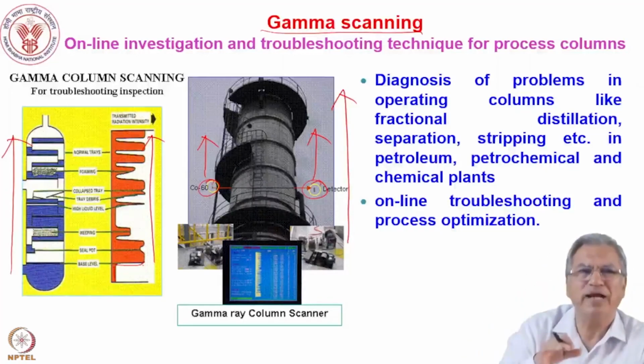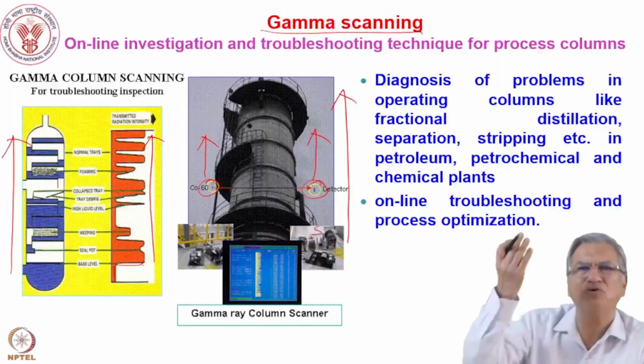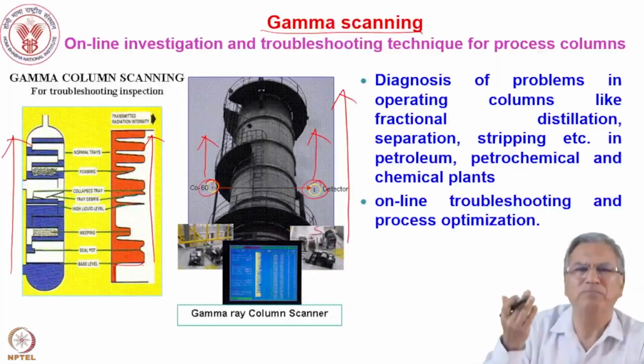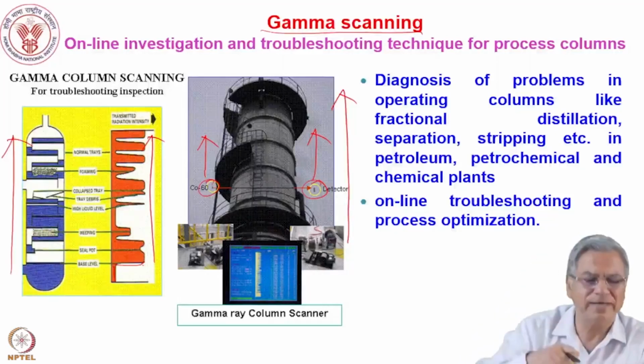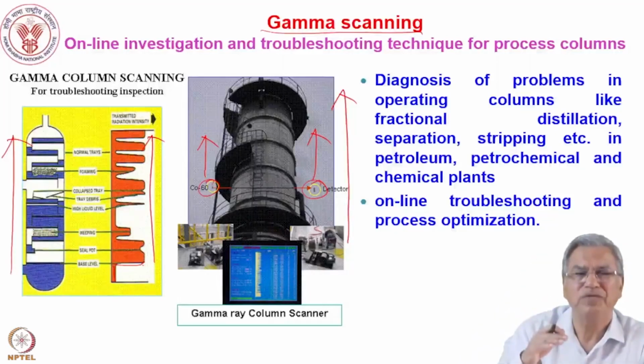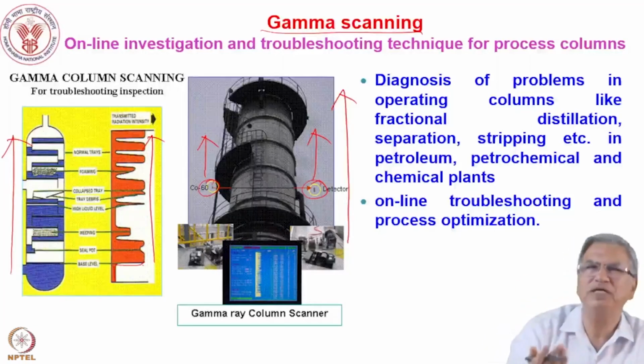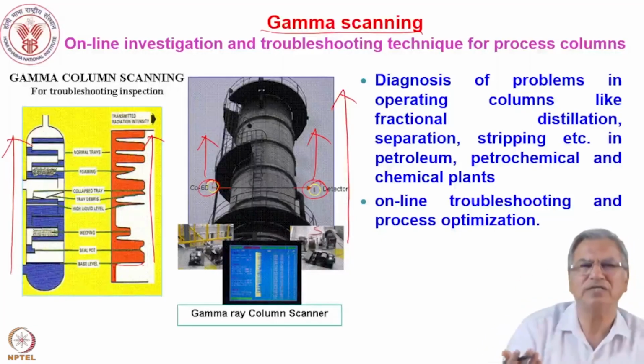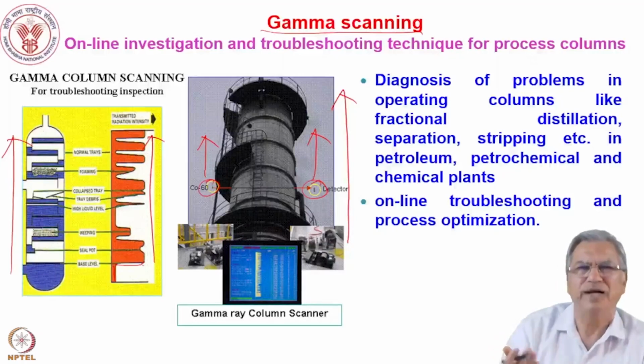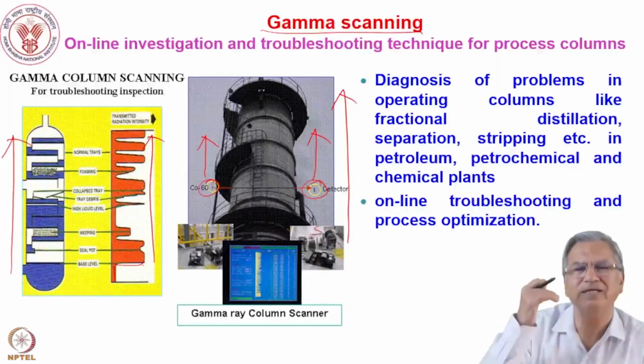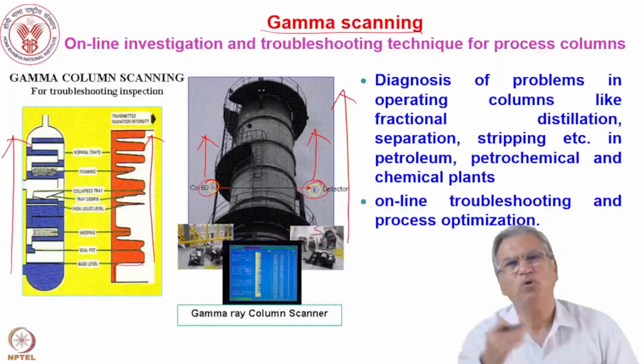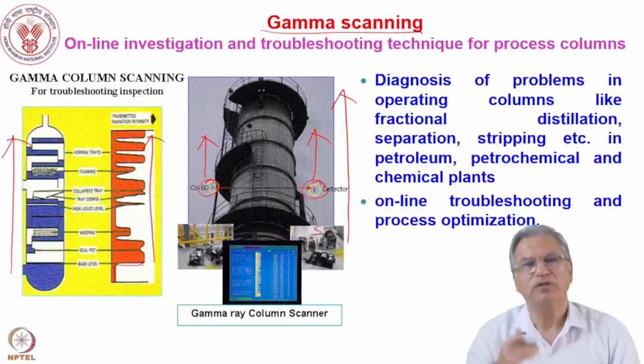If you take this profile at the beginning when the column was started, you can periodically monitor it, and if there's a problem in the plant, you can immediately run the scan and find the flaw. This scanning is very low cost: a cobalt-60 source and a sodium iodide thallium detector aren't expensive, manpower is just 1 or 2 personnel, and you can complete the investigation in a day. So you save time, money, and manpower, doing troubleshooting of plant problems very quickly and cheaply.